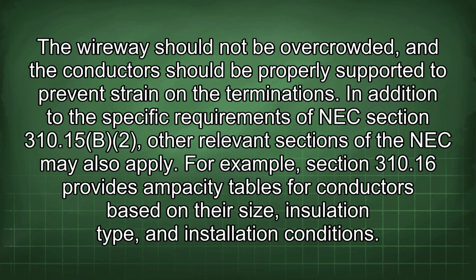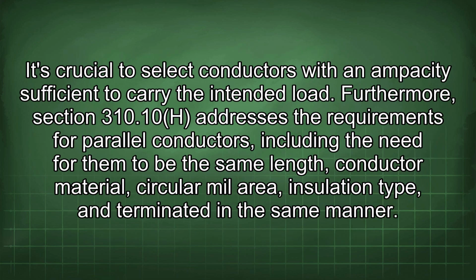In addition to the specific requirements of NEC Section 310.15(B)(2), other relevant sections of the NEC may also apply. For example, Section 310.16 provides ampacity tables for conductors based on their size, insulation type, and installation conditions. It's crucial to select conductors with an ampacity sufficient to carry the intended load. Furthermore, Section 310.10(H) addresses the requirements for parallel conductors, including the need for them to be the same length, conductor material, circular mil area, insulation type, and terminated in the same manner.